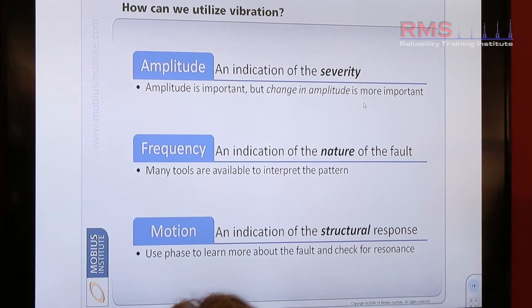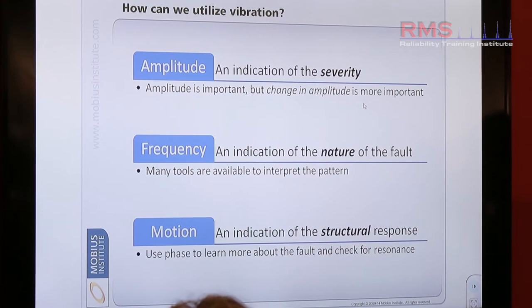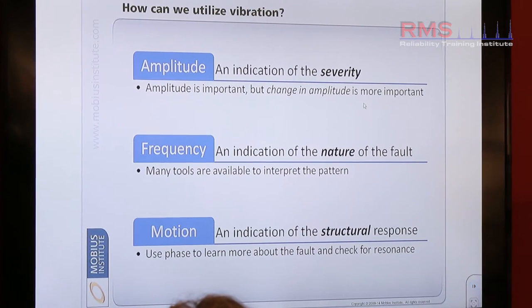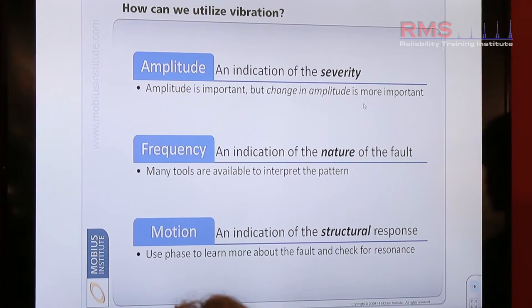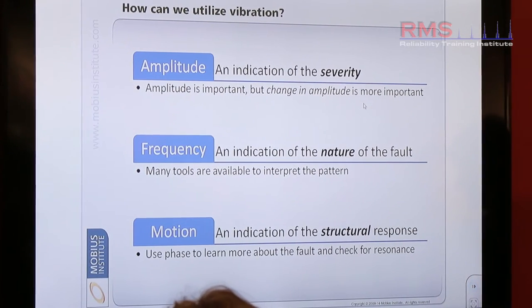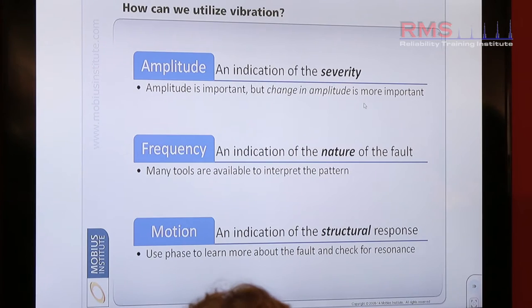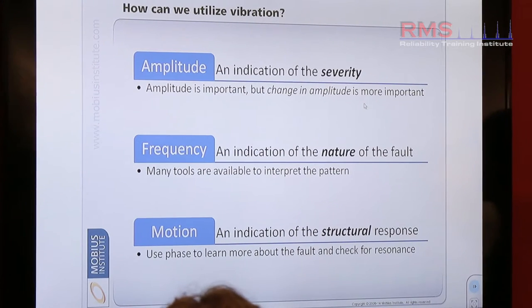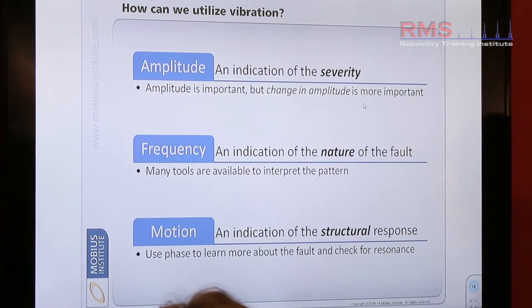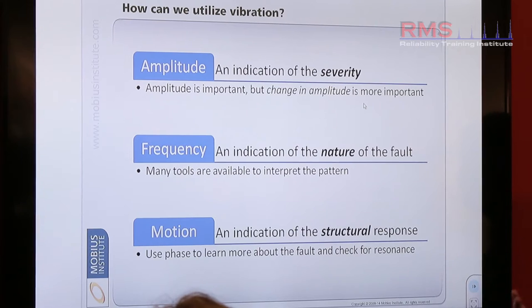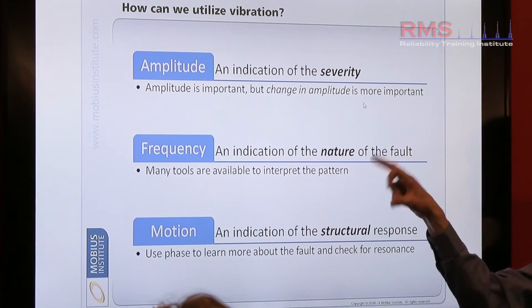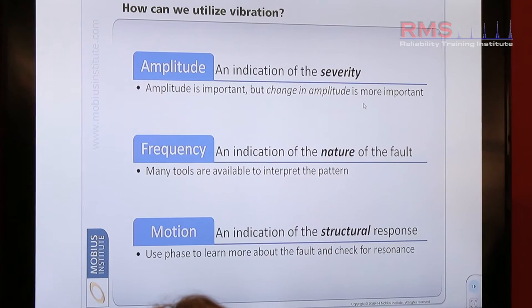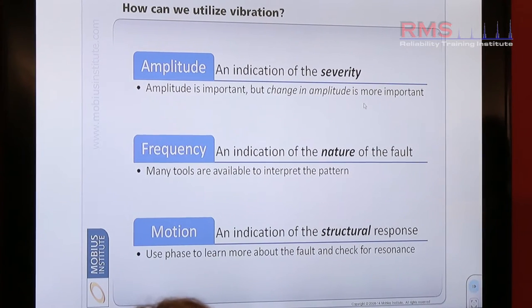Once that change occurs, we can say the vibration has changed — due to what? Well, that's where we need to understand the frequency, the rate of the heartbeat. Is it 25 pulses per rotation? Is it six pulses per rotation? Or is it one pulse per rotation? Depending upon what's causing it to vibrate. So the frequency enables us to understand the source of what's causing this thing to vibrate — the defect itself.